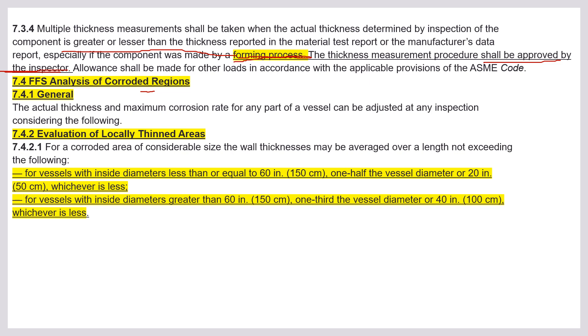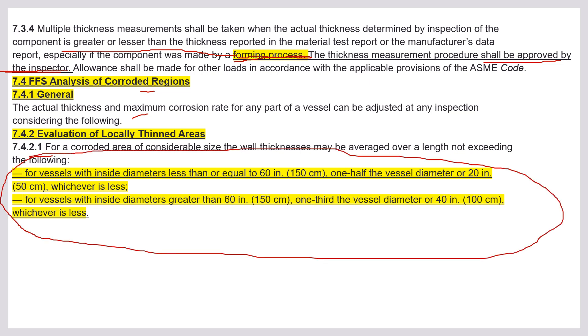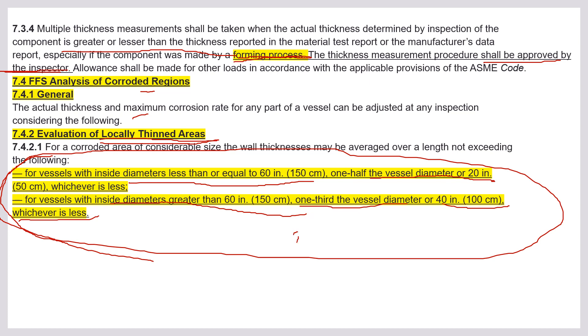Evaluation of locally thinned areas — this is a must question for the close-book exam. For vessels with inside diameter less than or equal to 60 inches, one half of the vessel diameter should be considered, or 20 inches (50 cm), whichever is less. For vessels with inside diameter greater than 60 inches, one third of the vessel diameter or 40 inches, whichever is less. For example, if the vessel diameter is 90 inches, one third = 30 inches; compared to 40 inches, you take 30 inches, which is less. This question is expected in both open-book and close-book exams.